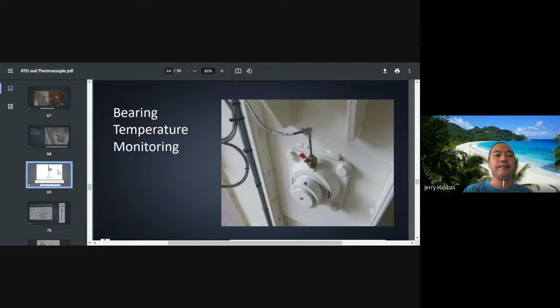Okay, so we go now to an example of a transmitter. You can see the head transmitter, which has inside a rugged type of enclosure or embodiment, supplied with plus and minus 24 volts. If it doesn't have that, usually with three terminals, then it's just a terminal block where you terminate your 3-wire or 2-wire RTD. But if it has positive and negative supply, it's a temperature transmitter.